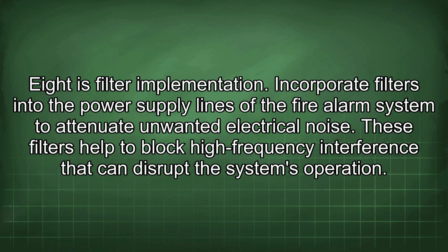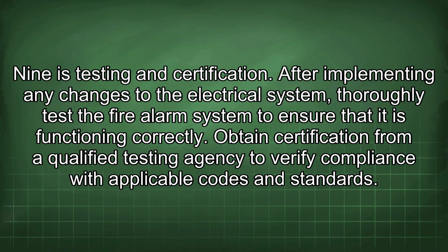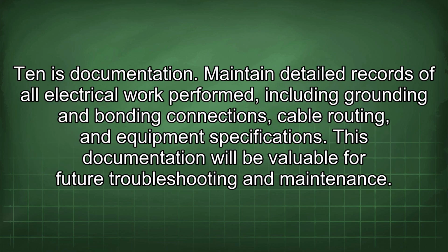Eight is filter implementation. Incorporate filters into the power supply lines of the fire alarm system to attenuate unwanted electrical noise. These filters help to block high-frequency interference that can disrupt the system's operation. Nine is testing and certification. After implementing any changes to the electrical system, thoroughly test the fire alarm system to ensure that it is functioning correctly. Obtain certification from a qualified testing agency to verify compliance with applicable codes and standards. Ten is documentation. Maintain detailed records of all electrical work performed, including grounding and bonding connections, cable routing, and equipment specifications. This documentation will be valuable for future troubleshooting and maintenance.